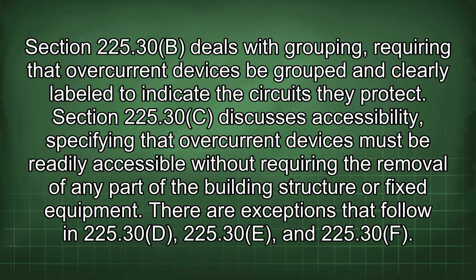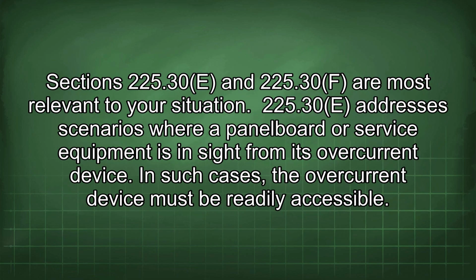Section 225.30c discusses accessibility, specifying that overcurrent devices must be readily accessible without requiring the removal of any part of the building structure or fixed equipment. There are exceptions that follow in 225.30d, 225.30e, and 225.30f. Sections 225.30e and 225.30f are most relevant to your situation.